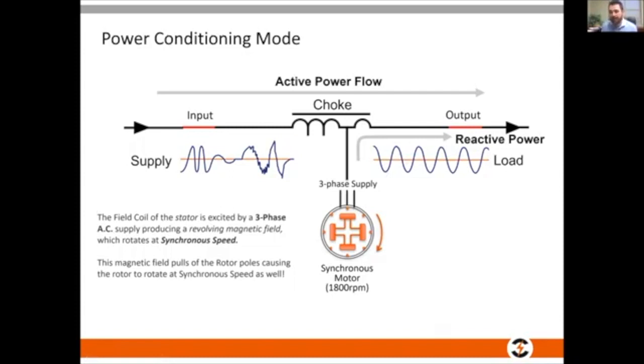It also means, because I have this synchronous motor, I'm automatically correcting the power factor because I'm supplying reactive power. So I'm going to have unity power factor on my consumer bus. I'm going to absorb harmonics to less than 2%. Both those generated by the consumer and those entering from my utility, they're going to flow through to my low impedance machine. And of course, I'm going to provide you all the benefits of voltage stabilization. So that's why I say we have this superior load handling.